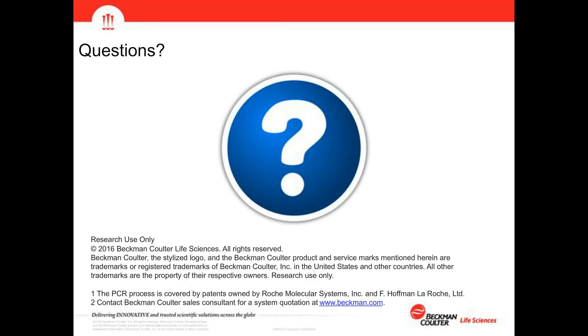What's the pipetting volume range for your system? I can handle that one too. For the Biomek 4000, we can pipette anywhere from 1 to 1,000 microliters, depending on the tip that's loaded and the head that's used. For a 1 microliter transfer with a P20 tip, the inaccuracy is 5%.